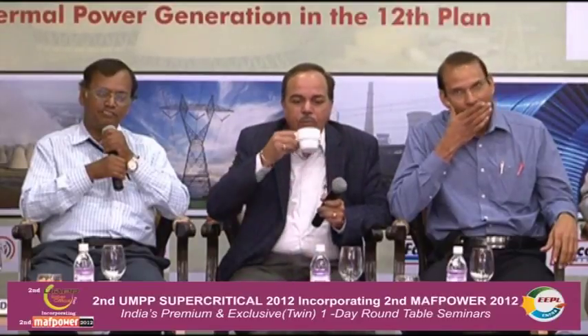Purely based on HBD, let me put it more technically - what does your heat balance diagram say, if I draw it at 85% for subcritical versus supercritical, what is the difference? If you talk about 80% load - between BMCR to 80% load, the temperature is always maintained at the rated value. Superheater is 568, reheater is 596. It's maintained up to 60% or even 50% of the load.